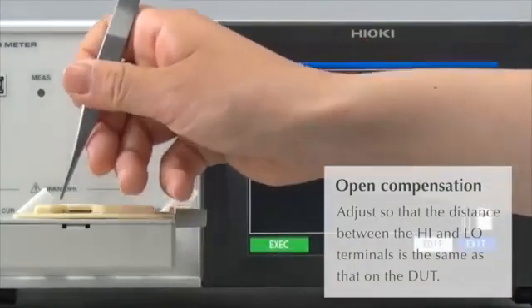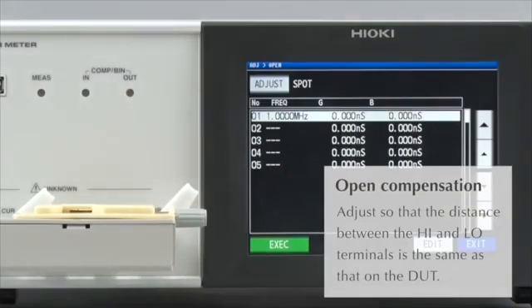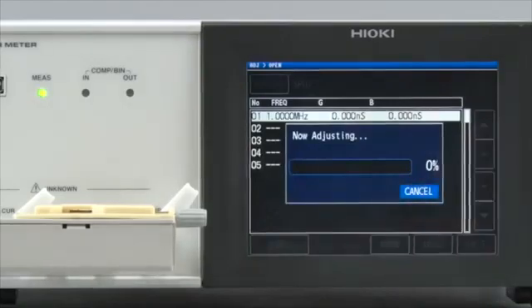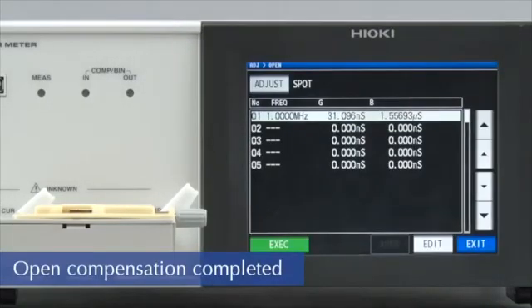By doing this, you will be conducting open compensation with the electrodes spaced at exactly the same distance as that on the DUT. This completes open compensation at 1 MHz.